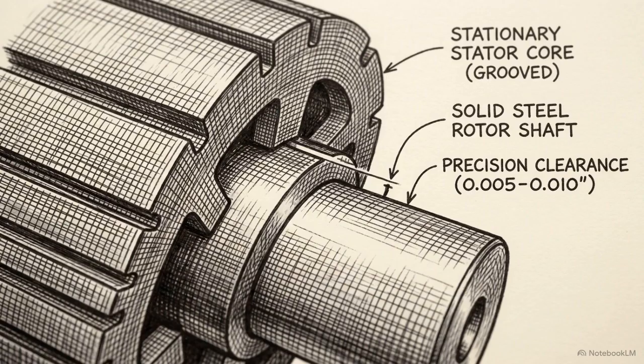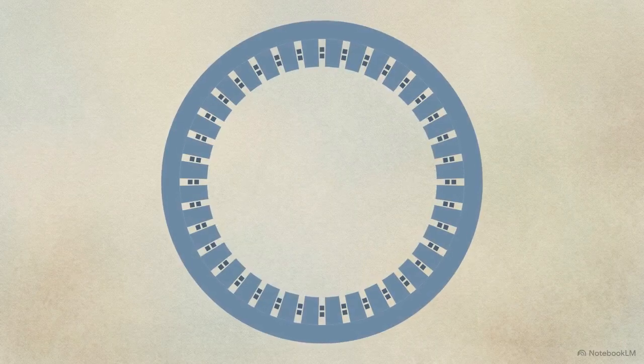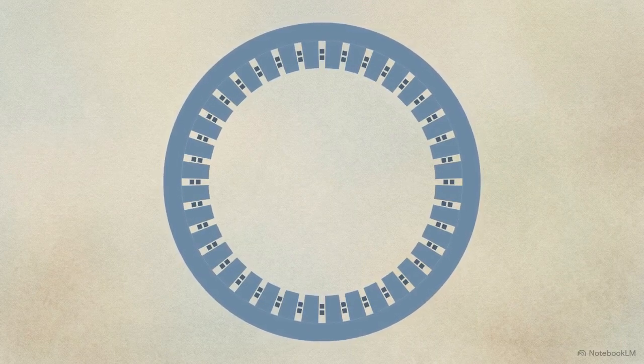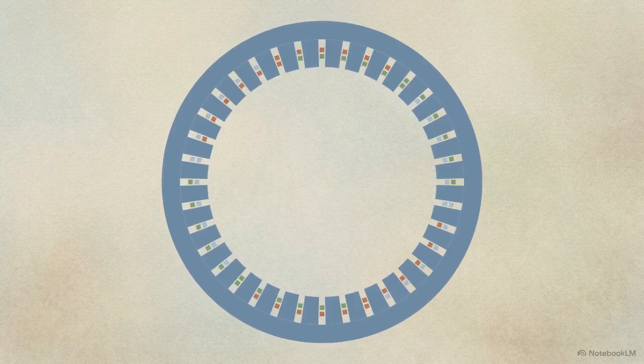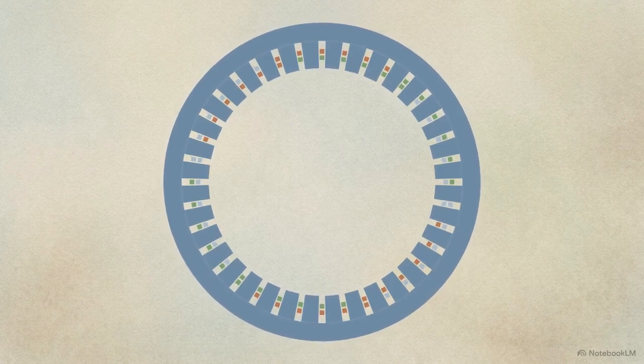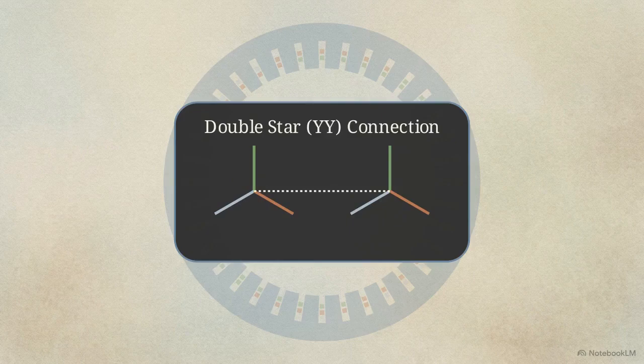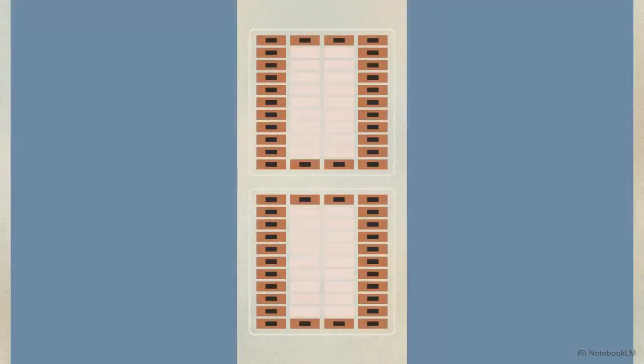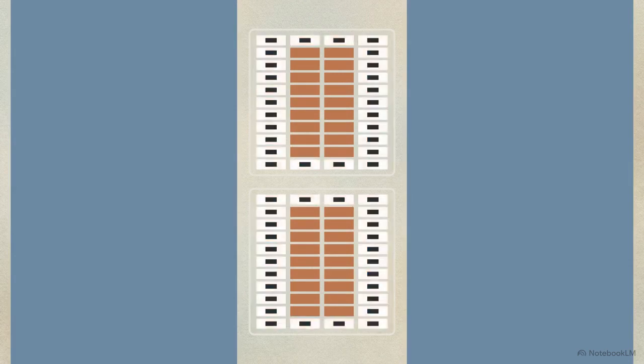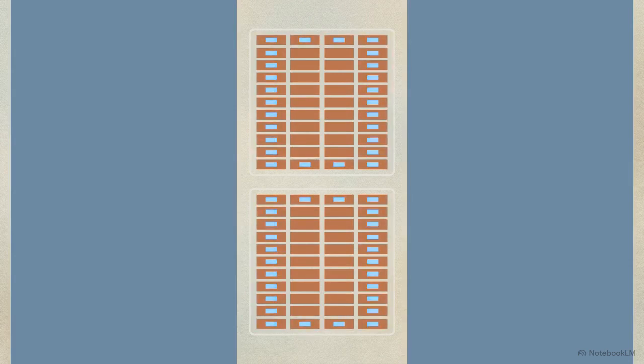Passing through the gas-tight steel casing reveals the two primary structural bodies, the central immovable stator core and the high-speed rotating shaft. This cross-sectional diagram details the stator winding architecture. It utilizes a three-phase setup with two parallel circuits. The double-layered conductors use a double star connection. Zooming in to a single slot reveals both solid copper conductors and hollow copper tubes to facilitate direct internal fluid cooling.